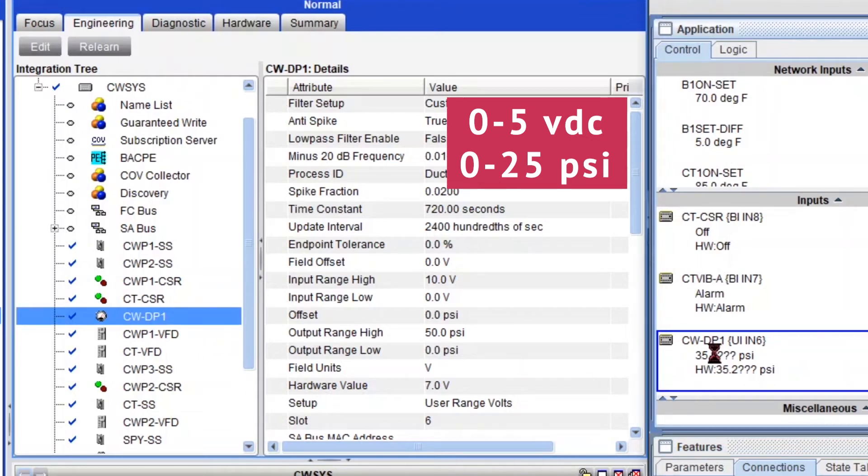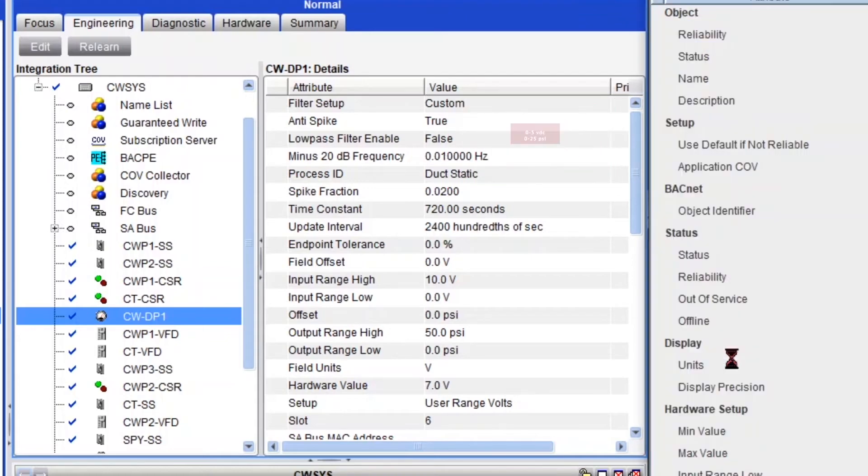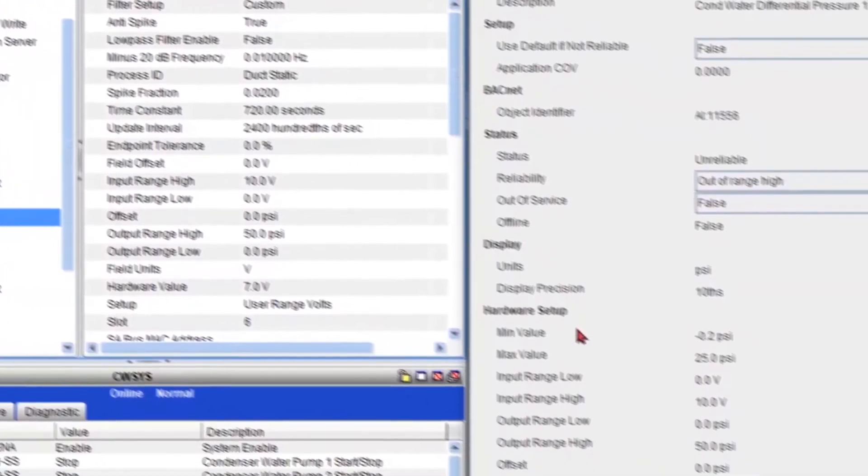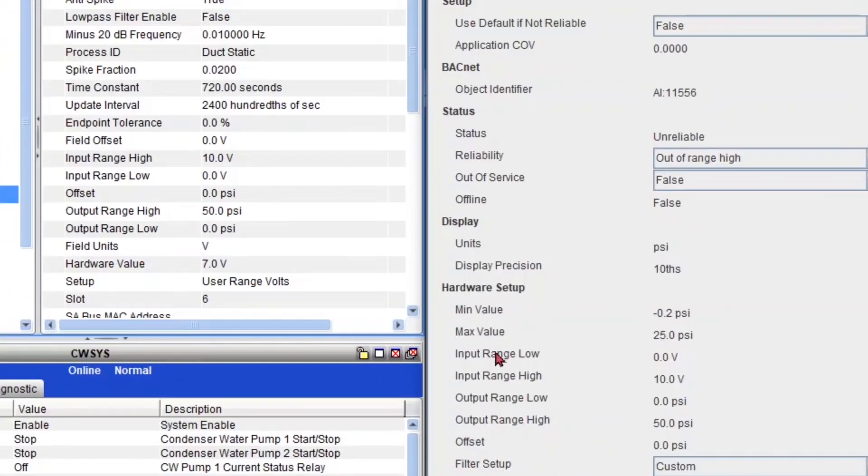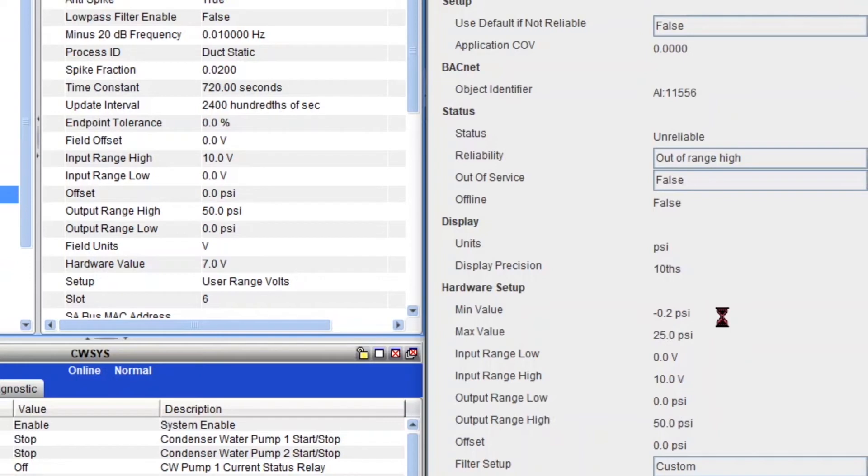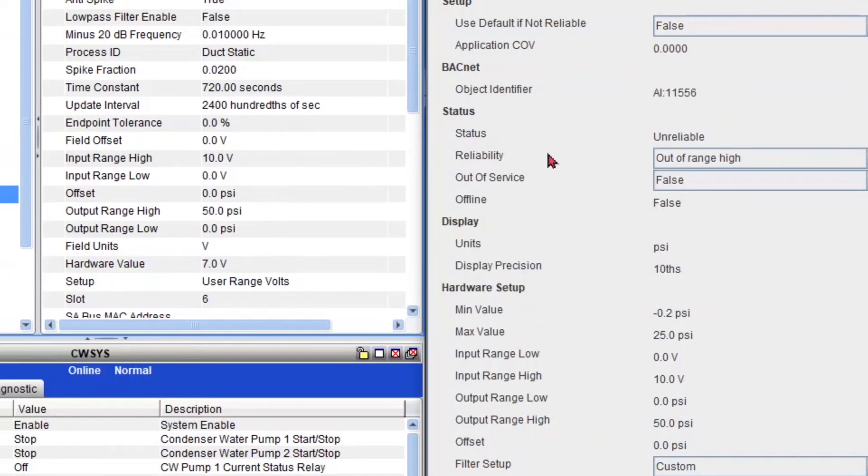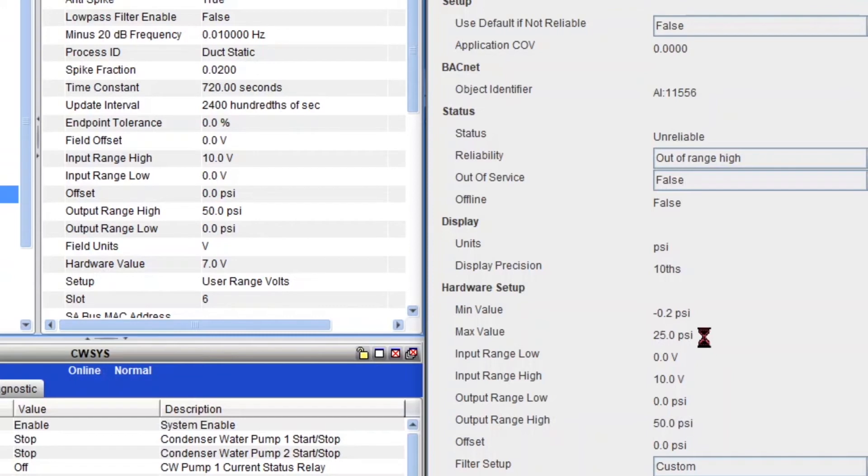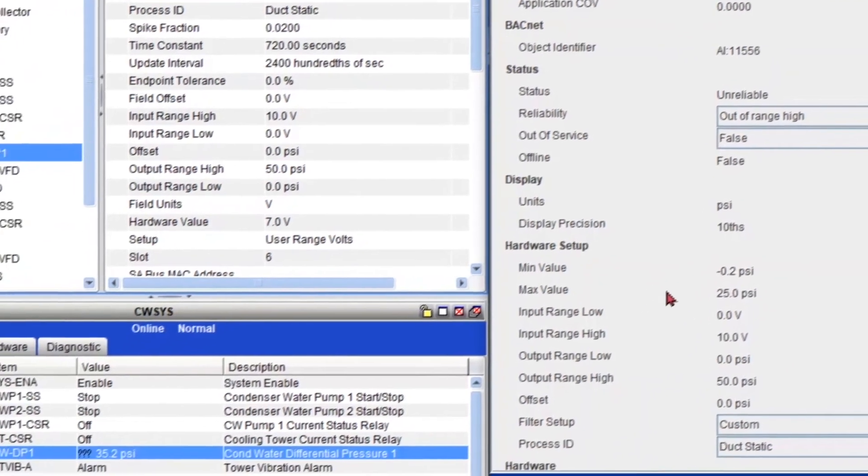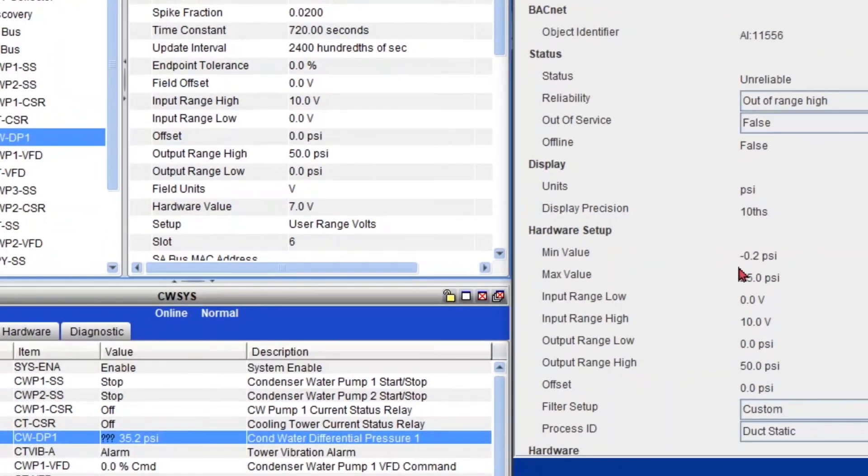And let me open that sensor here as well. And I also want to explain you what's the difference between these min and max values and the output range low and high, because both have the same units, PSI. So my min and max values, they actually define the reliability of the point. And you can see under my status that it's unreliable. And what's the reason? The reason is that it's out of range high, meaning that its actual value is reading higher than the maximum value that you are allowing here. So it's actually reading 35.